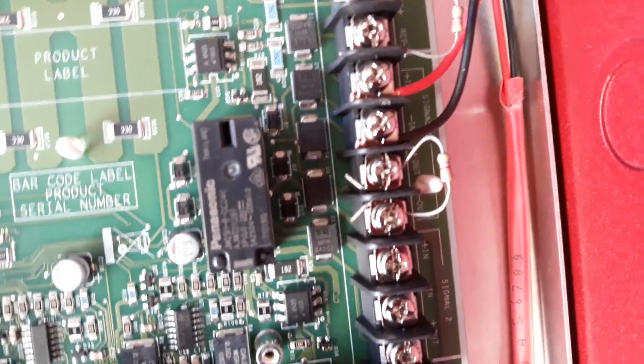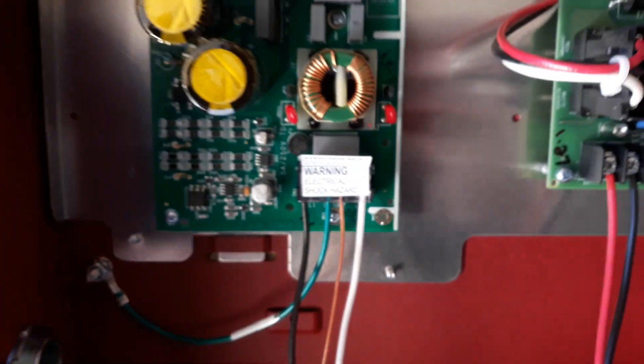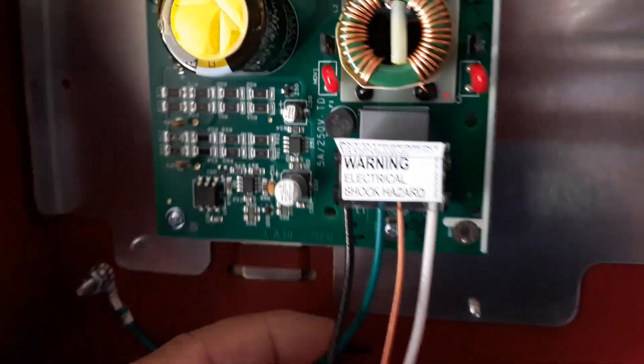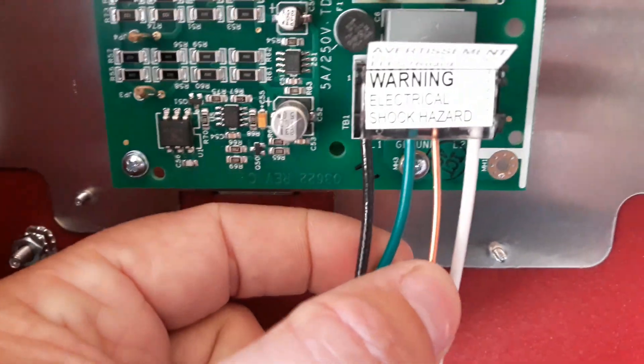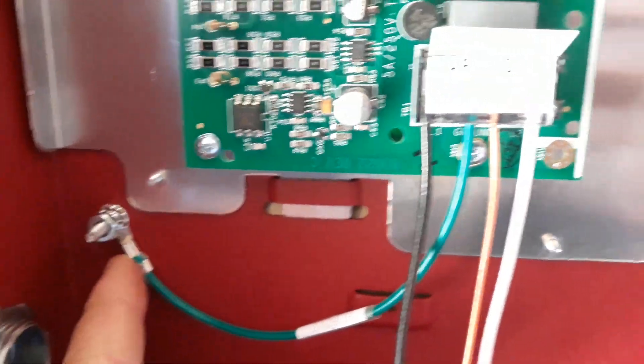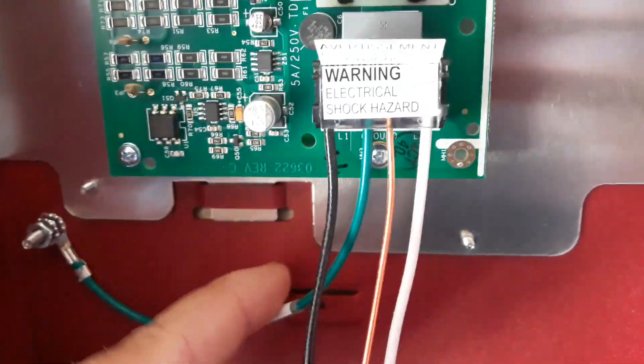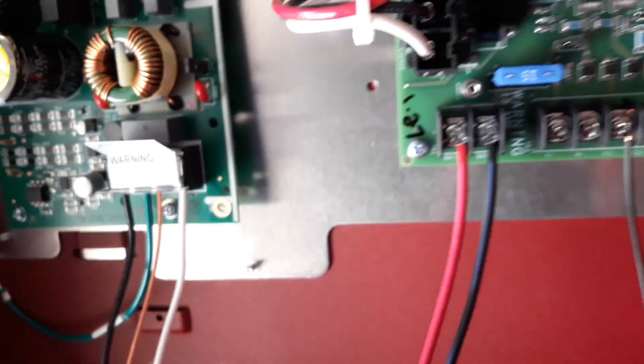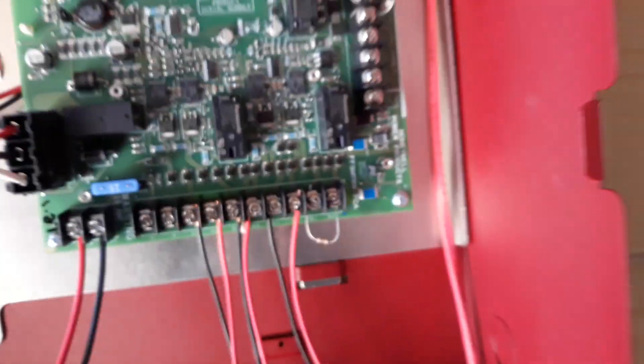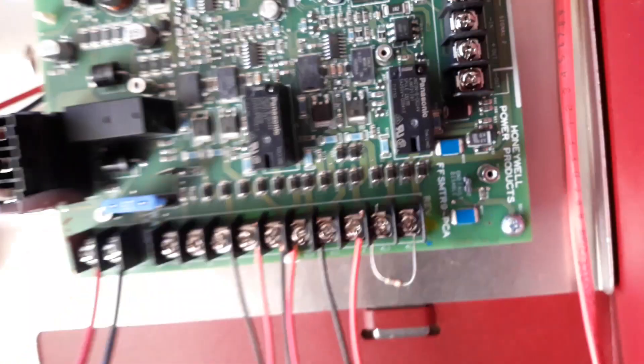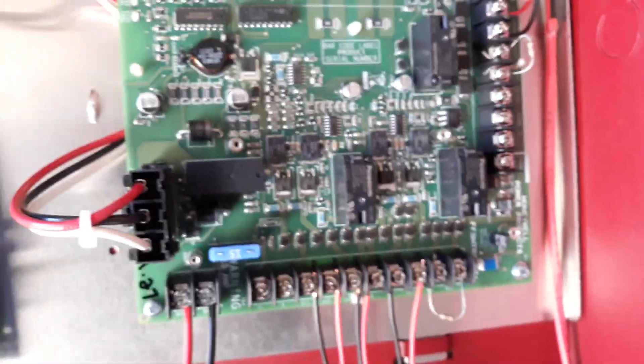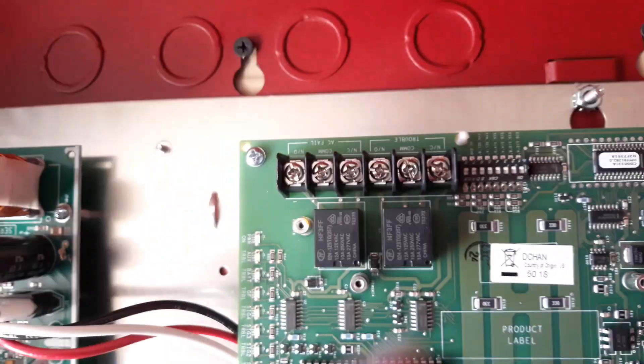It monitors your troubles through the circuit itself. It bonds your ground to the panel right here. I like that. It comes like that with the factory. Like I said, I never disable ground fault detection. You know, if it's got ground fault on it, replace the panel.